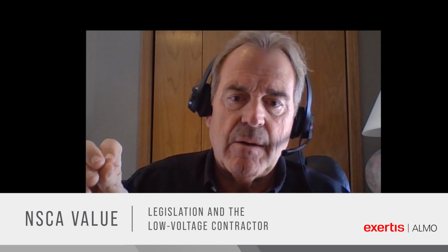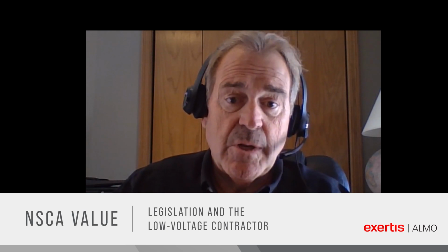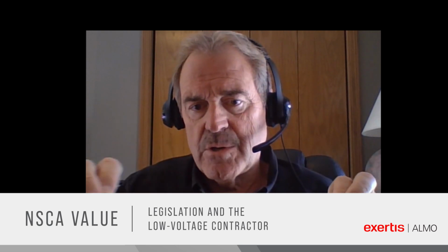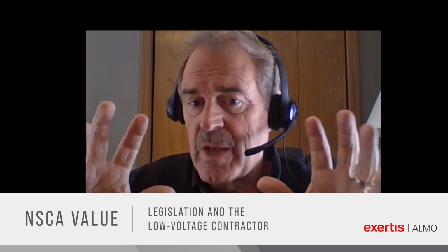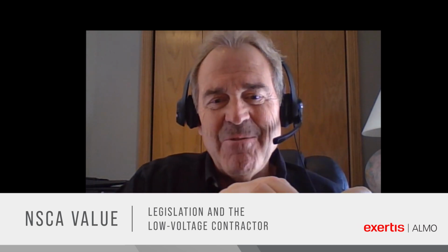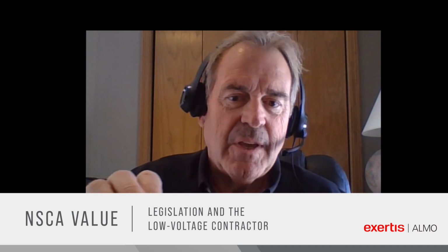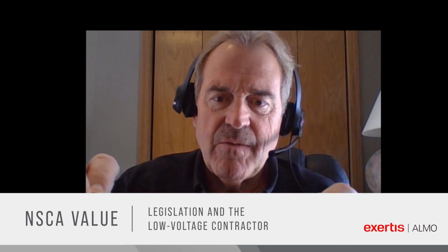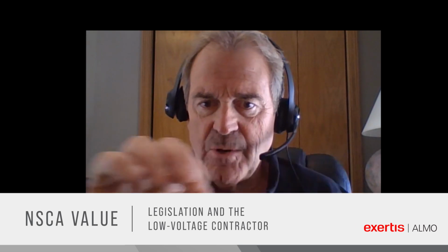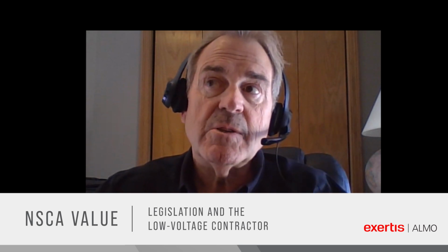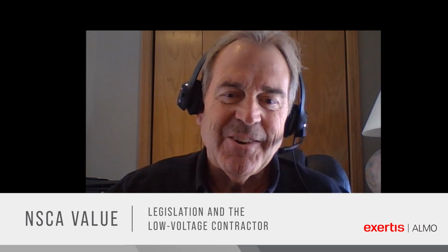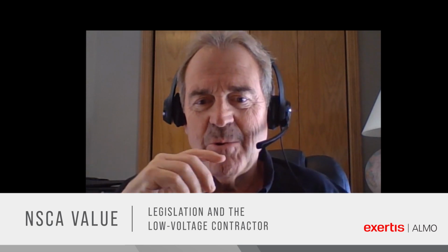My big thing is removal of abandoned cable. A systems integrator, by way of the code, is responsible. They are the responsible party for the removal or proper tagging of abandoned cable. A lot of integrators, not NSCA members, but a lot of the other ones, don't understand the code well enough to know that it's their obligation in a renovation to remove abandoned cable for systems that aren't used anymore. They put in their quote something like, it's going to be the responsibility of others to remove and tag abandoned cable. Well, the AHJ doesn't care. You're going to end up doing it, whether you put that in your quote or not.